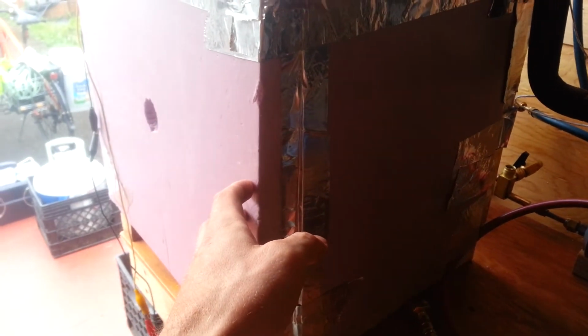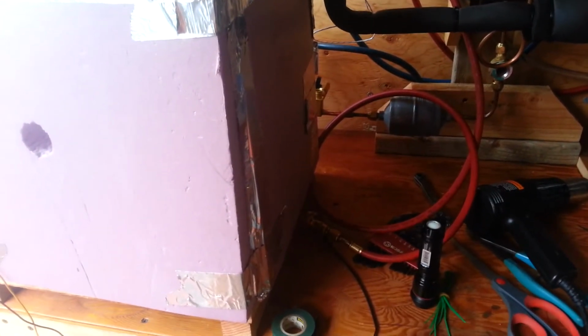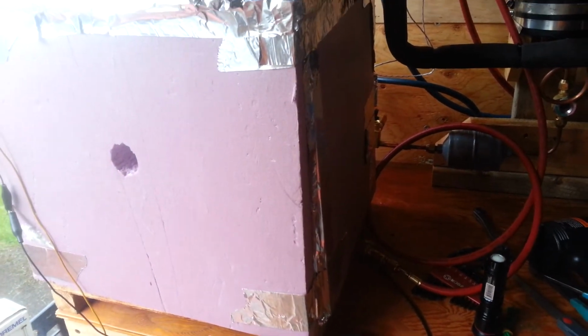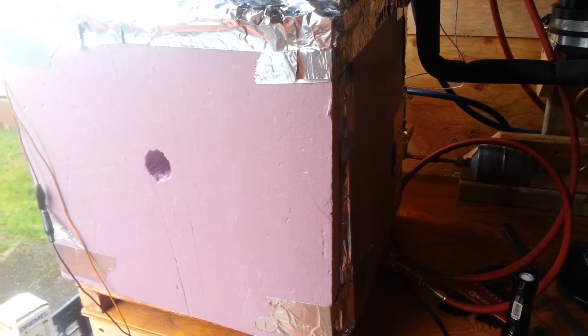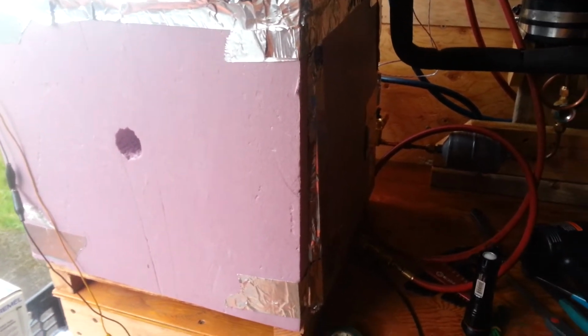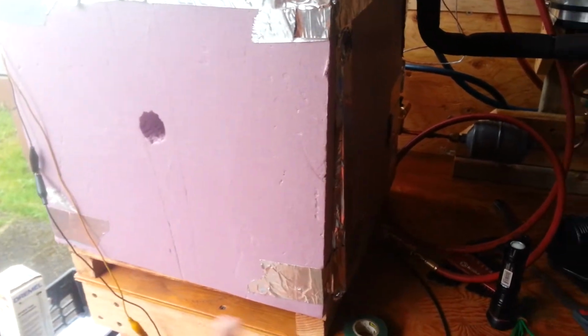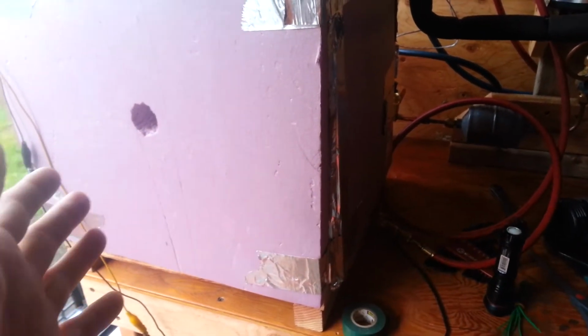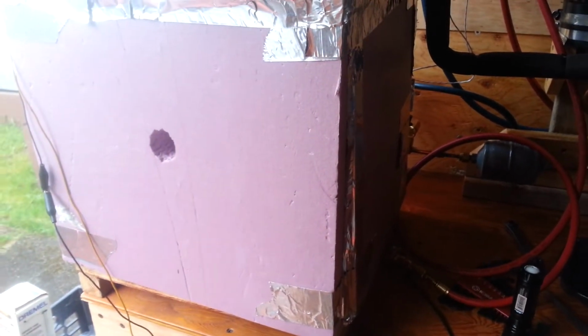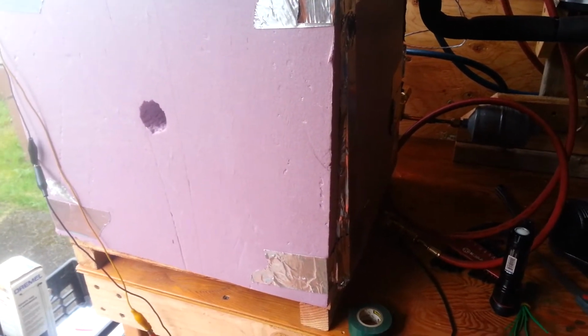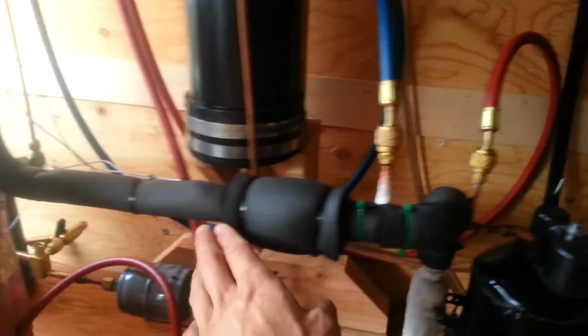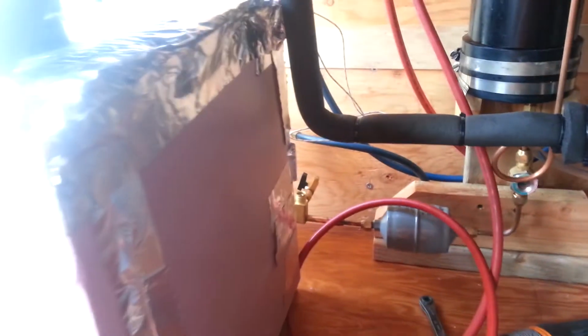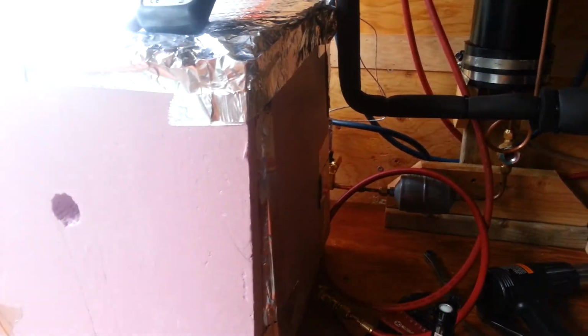And the reason for that is because this is a gravity-flooded evaporator. The suction gas being taken back to the compressor is always near saturation. And the reason for that is the fact that the evaporator is always in a flooded condition. I mean, it's a flooded evaporator. A dry evaporator, the type where you see it has all the coils with a TXV, the TXV regulates the amount of refrigerant going into the coil based on the amount of superheat being produced. If you were to flood the thing, you could actually have liquid refrigerant going back to the compressor, which is a very bad thing. On the other hand, if it didn't admit enough refrigerant, it's going to dry out.